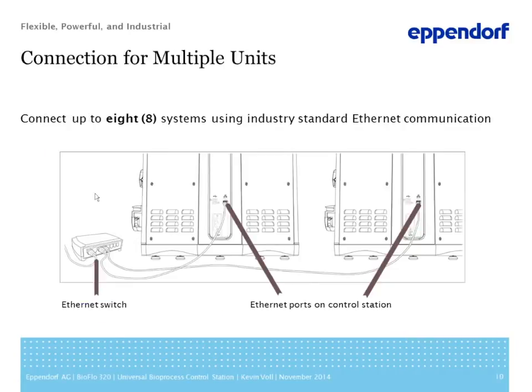A connection for multiple units: this is new for us, new for Eppendorf. We typically had always worked with master and utility stations. Now we take the same control stations, and over an active IP network, we use Ethernet communication to connect up to 8 units to a single interface. Previously, we could connect only 4 units to a single interface.